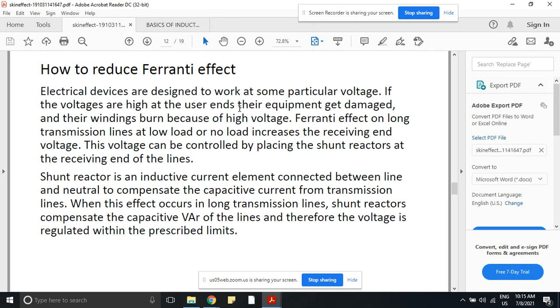But you are getting a voltage greater than 230, that means 250, 260, 280, like that. Then our equipments will get damaged and their windings burn because of high voltage. So the Ferranti effect on long transmission lines at low load or no load increases the receiving end voltage, and this voltage can be controlled by placing the shunt reactors at the receiving end of the lines. That means whenever the receiving end voltage is greater than the sending end voltage, at the receiving end we are applying our lightly loaded conditions.